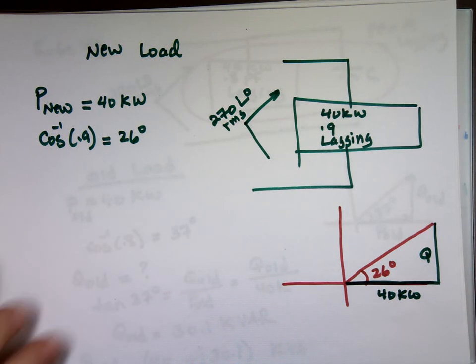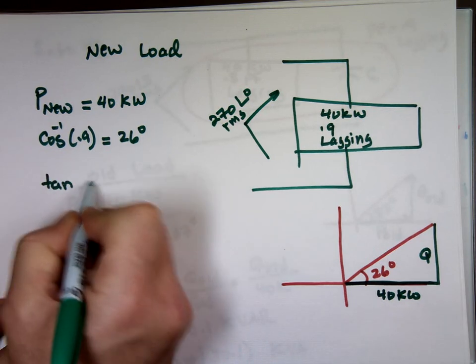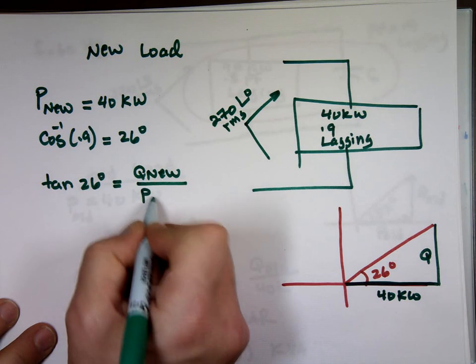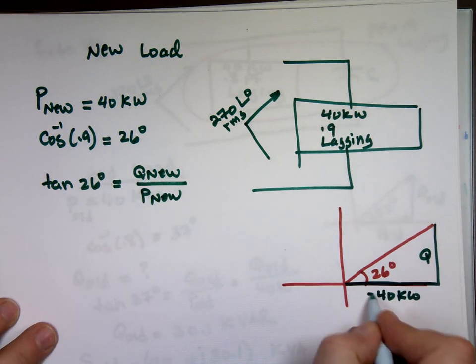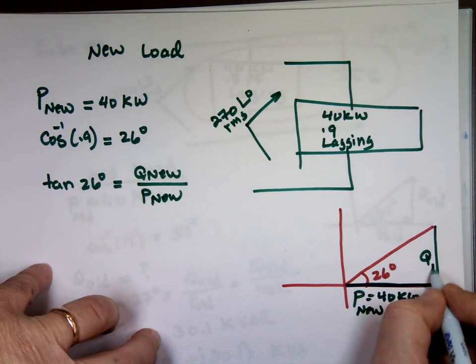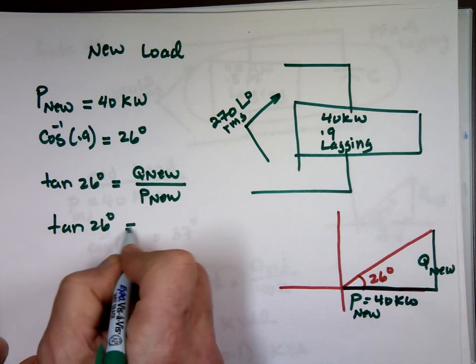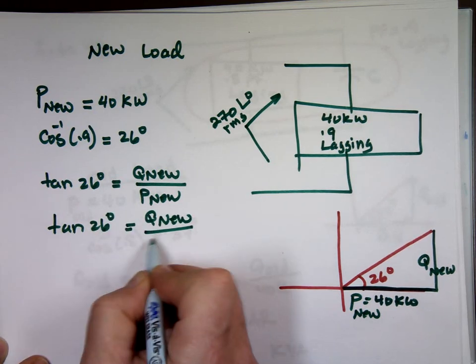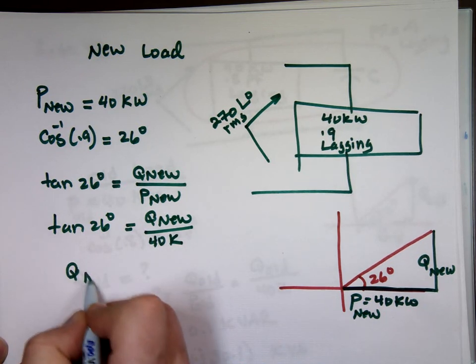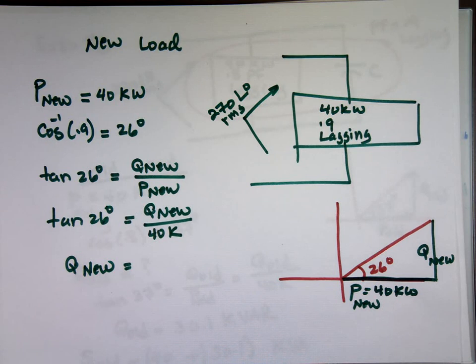The same thing. Tangent 26 degrees equal Q new over what? P new. The opposite over the adjacent. Tangent 26 equals q, the new value of q, over 40k. Can we get what q nu is? Tangent 26 degree times 40,000. 19.5k var.